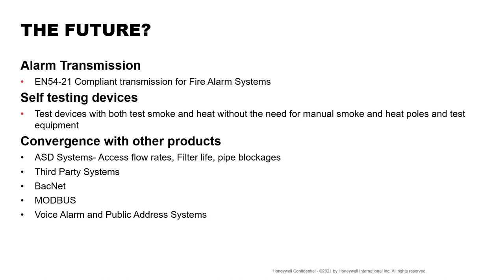Once again, it's a voice alarm. It's part of the life safety system, and it's controlled. You can see the condition and the health of it through CLSS, through the Connected Life Safety Services. It looks after them, so it can all be maintained. If you get a break in one of the sounder circuits, it can tell you.